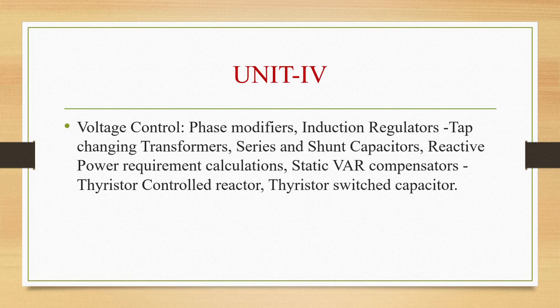So load is always changing, and voltage variation will be there at the consumer's premises. So when the load on the system increases, voltage at the consumer's terminals will fall due to increased voltage drop in alternator synchronous impedance, transmission line, transformer impedance, feeders and distributors.